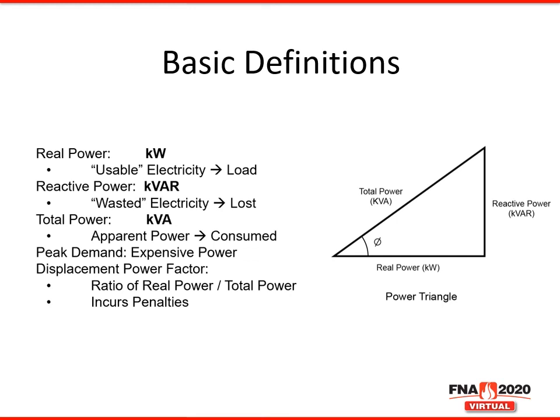There are three components that we looked at during this case study. One is the total kilowatt hours, which is a billable quantity, the peak demand, which is the most amount of current drawn and has associated penalties, and the displacement power factor, which can make energy more expensive.